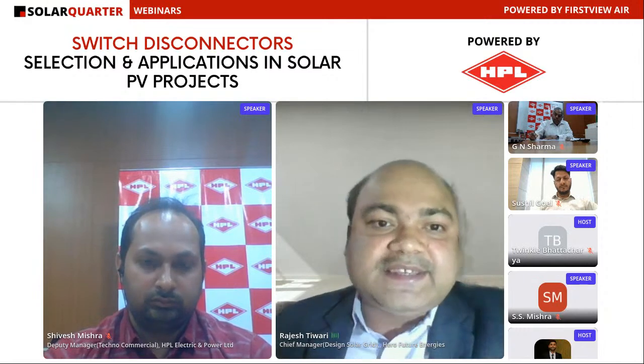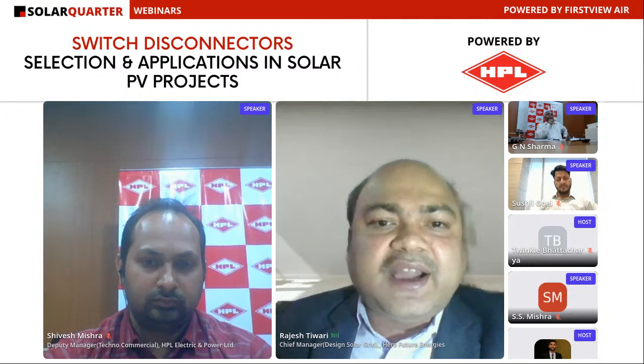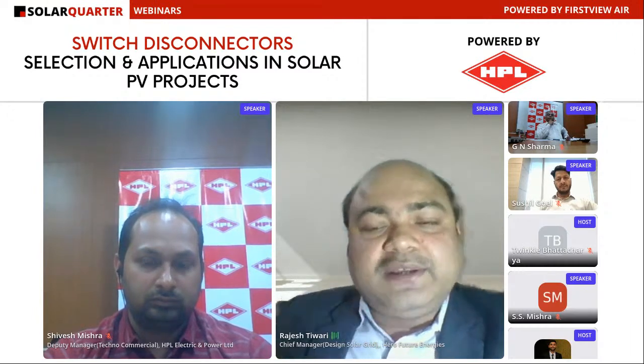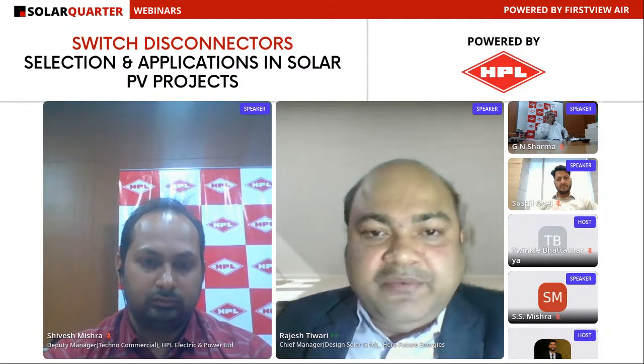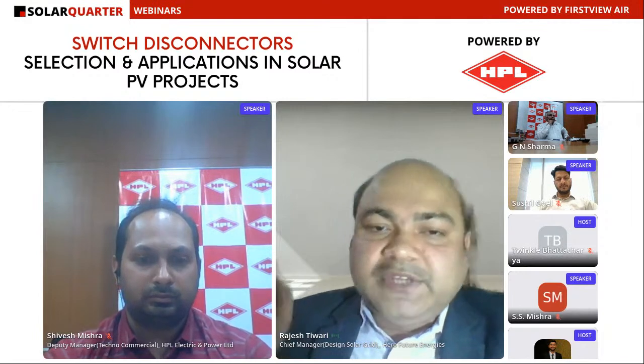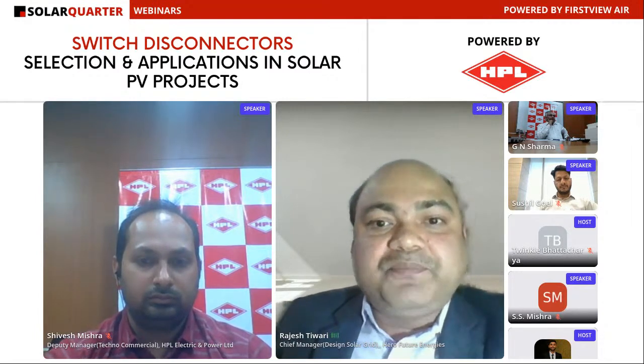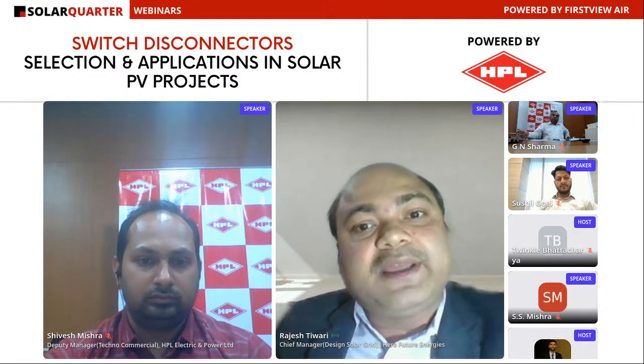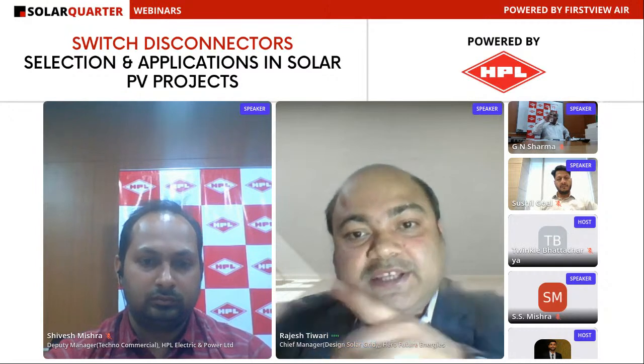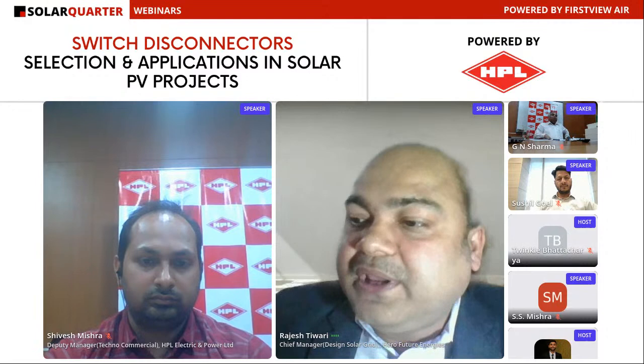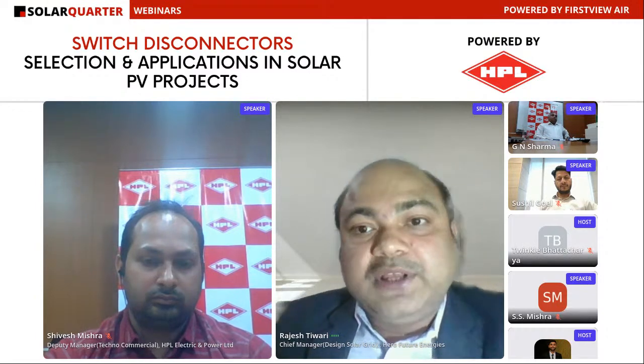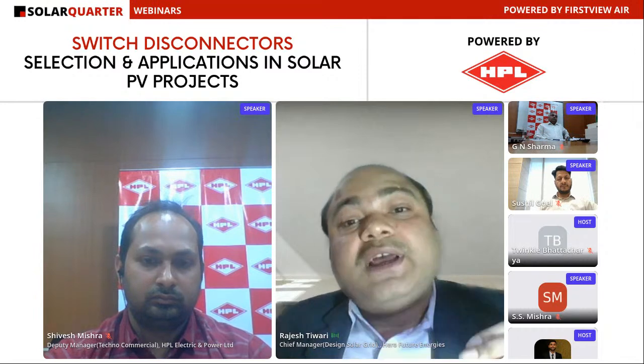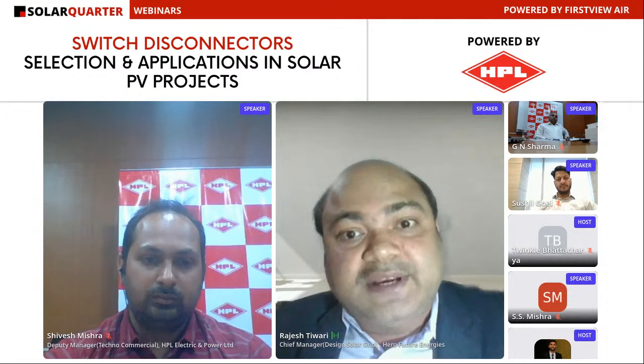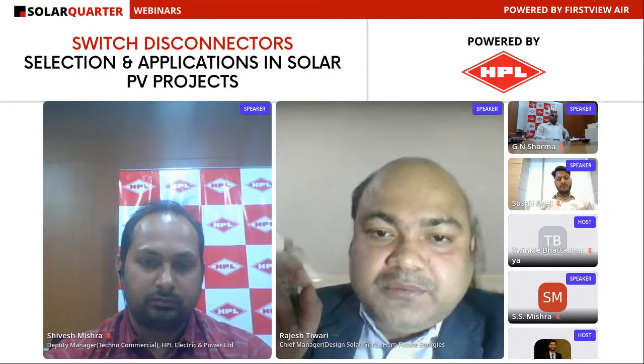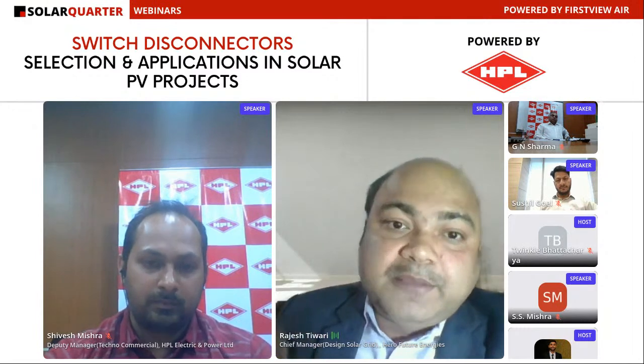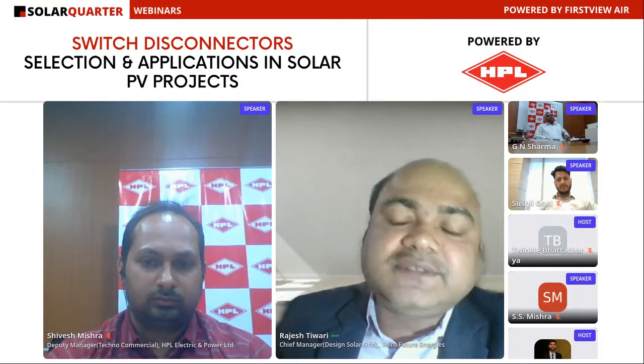But on the AC side, this 800 volt is a very unfamiliar product. It is non-standard, basically, because the inverter supplier came with 800 volt and gave it to us. In 800 volt there are only a few suppliers, and among them only one supplier can prove the design aspects in terms of the LT panel. So my request will be to HPL: if you can develop the type of scenario which is actual at the Bhadla side or the Rajasthan side, because you have to measure the temperature with a probe on the MCCB, the terminal, every point.